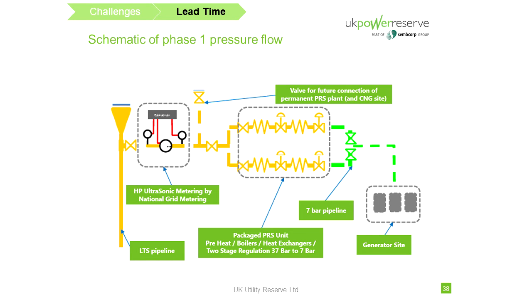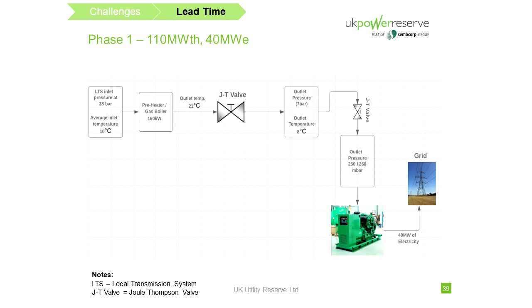and then down to the generators. That's exactly what I just put together in terms of the flow, which is an inlet of 38 bar, down to the pressure reduction, down to the preheater, which increases the temperature of the gas, and then down to making use of a Joule-Thomson valve, which then drops down to 7 bar, and then we're having 40 megawatt of electricity generated into the grid.